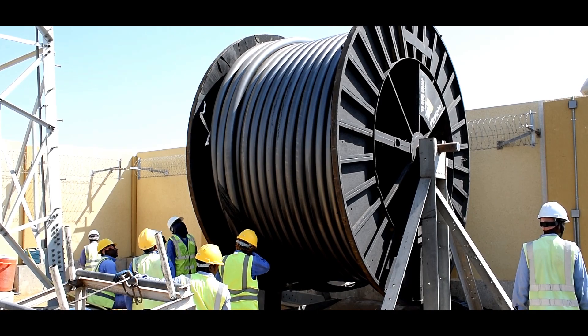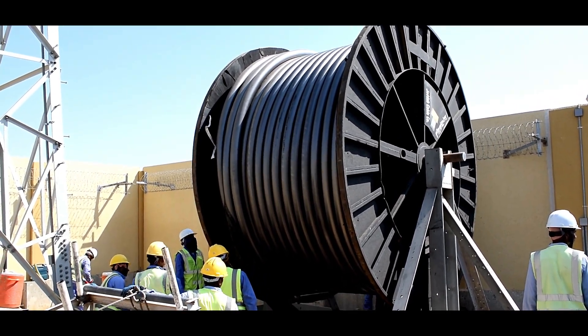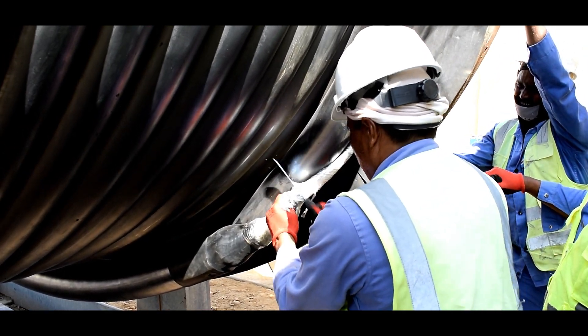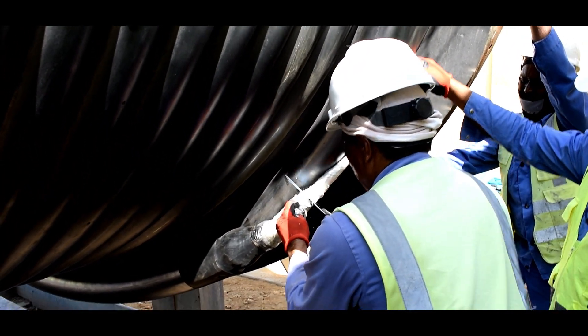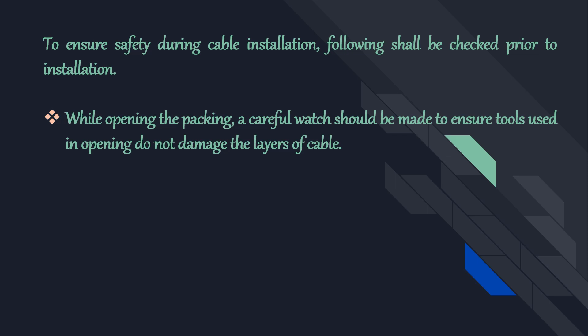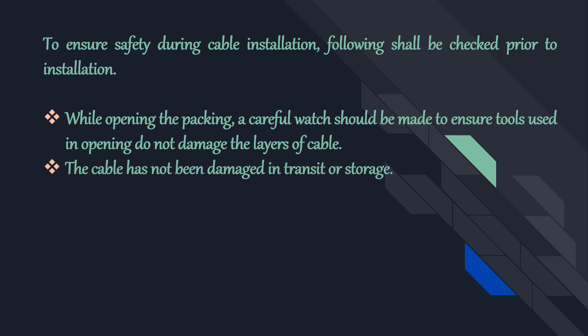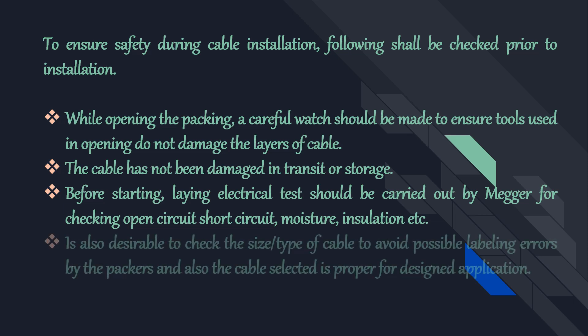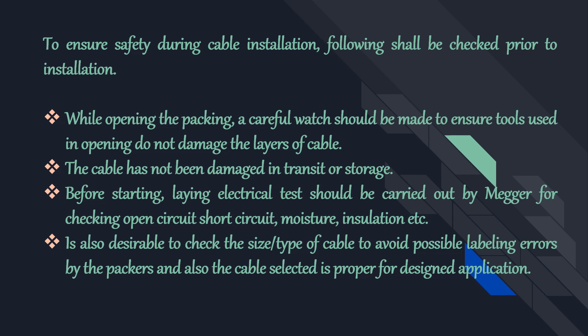To ensure safety during cable installation, the following shall be checked prior to installation. While opening the packing, a careful watch should be made to ensure tools used in opening do not damage the layers of cable. Check that the cable has not been damaged in transit or storage. Before starting laying, an electrical test should be carried out by Megger for checking open circuit, short circuit, moisture, and insulation. It is also desirable to check the size and type of cable to avoid possible labeling errors by the packers, and to confirm the cable selected is proper for the designed application.